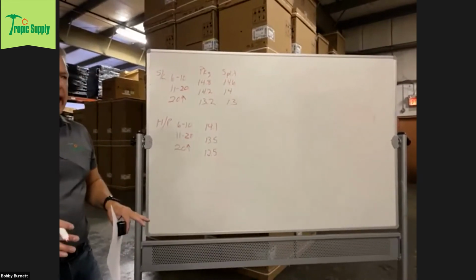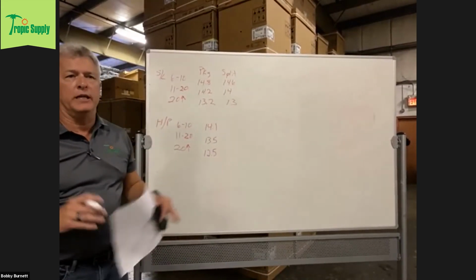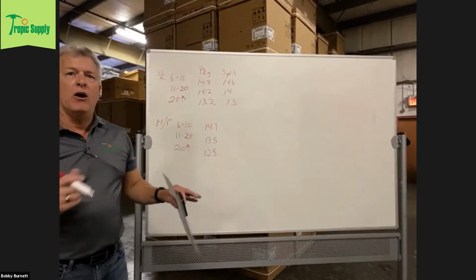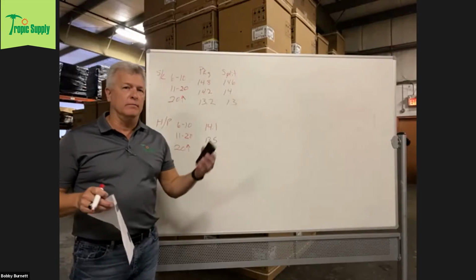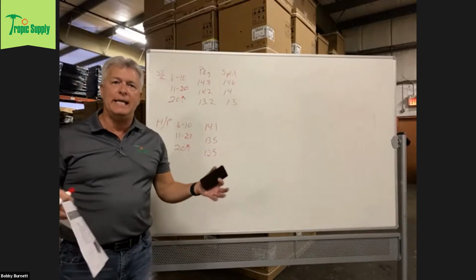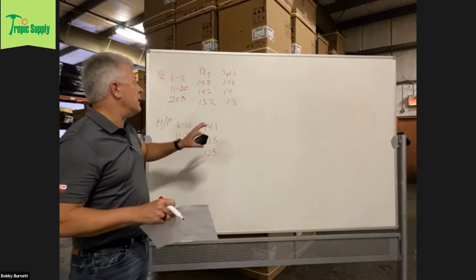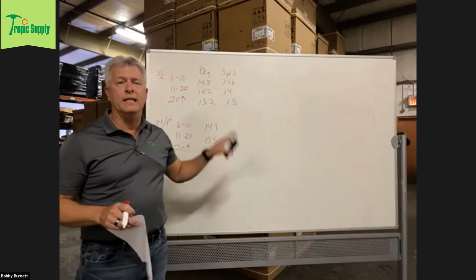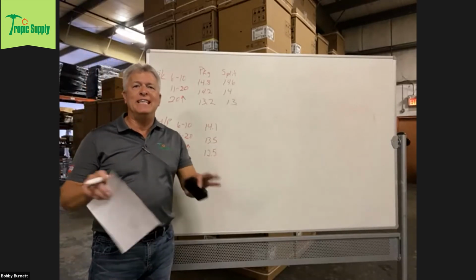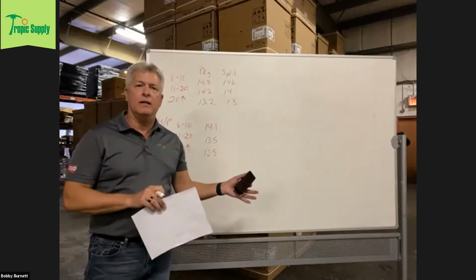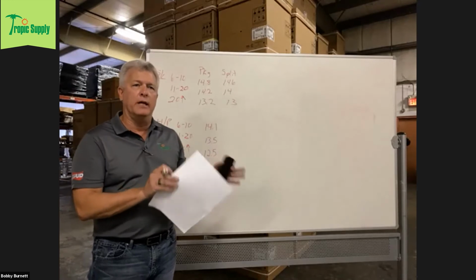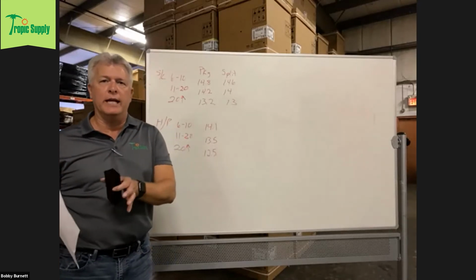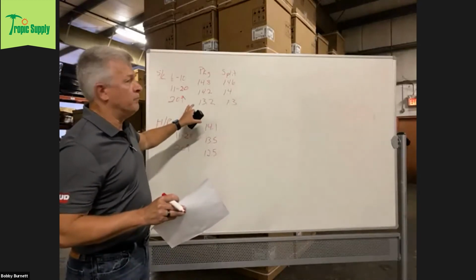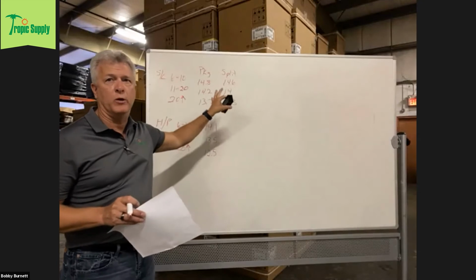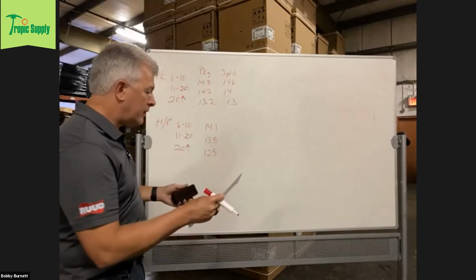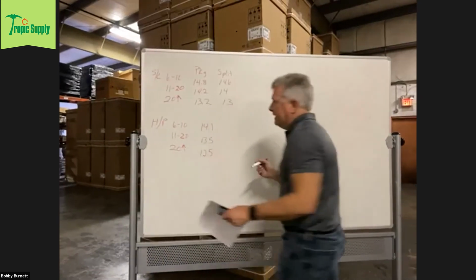When you're looking at a residential system that's got a SEER rating of 15, its EER rating is going to be lower than that, usually as low as 11, 12, maybe 13 EER. So even on the residential stuff, hitting a 14 in this IEER, some of your 15 SEER systems from some manufacturers may not even hit that. So we're really talking about a jump from 14 SEER equipment up to possibly 16 SEER equipment on the residential side. And on the commercial side, we're jumping from what was 11 and 12 EERs up to these 14 IEERs.